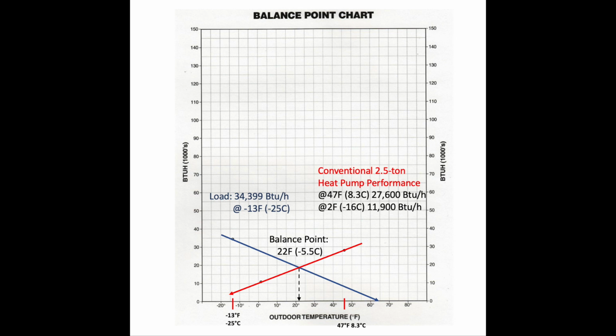Oh, yes, Doug. This is a balance point chart. This is something that we probably don't need to do anymore because electronics largely solved the problem of which unit is going to operate at what time. We now have hybrid systems that decide whether the heat pump or a gas furnace should operate. But the balance point chart is something we used to do in the early days of heat pumps, conventional heat pumps. That's the non-inverter, non-cold climate compressors. So what we would do is, of course, we need an accurate load calculation.